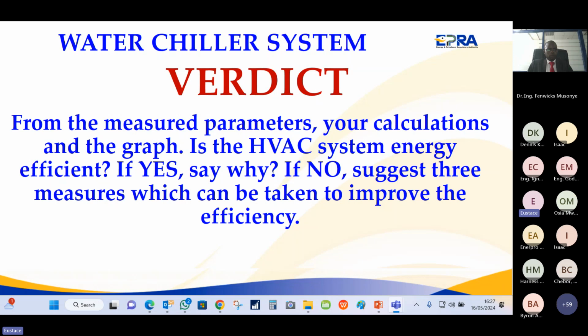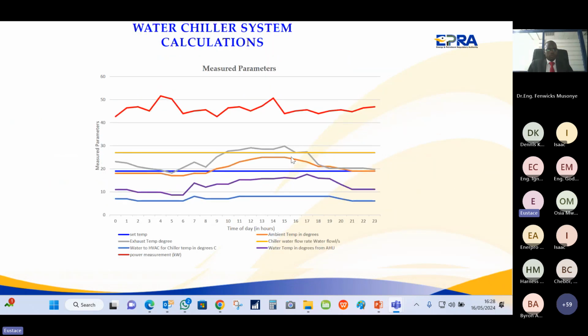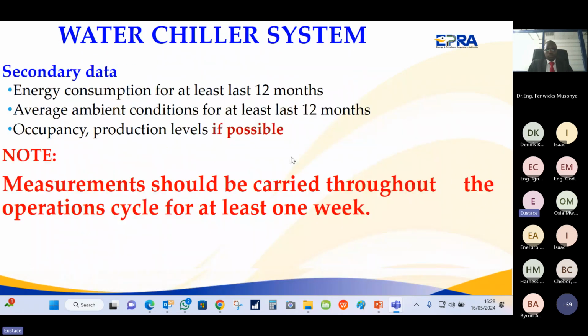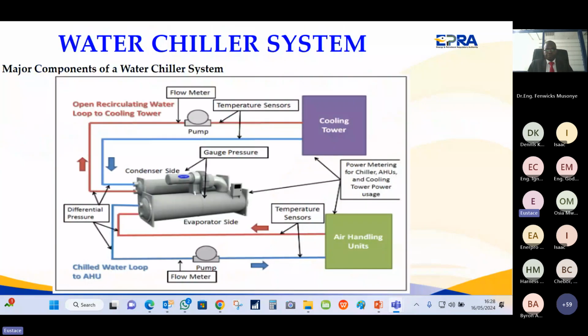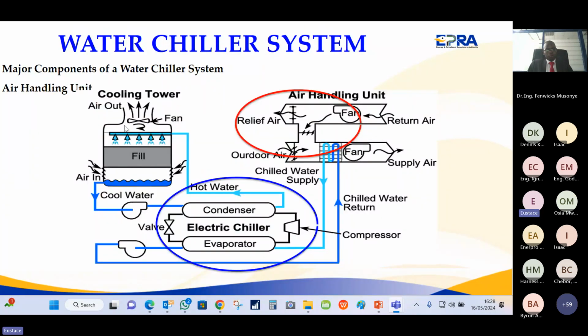The other point is, during this time you can bypass the chiller, which consumes a lot of energy. The compressors are the largest energy consumers, right? You can bypass the chiller and use the cooling tower instead.